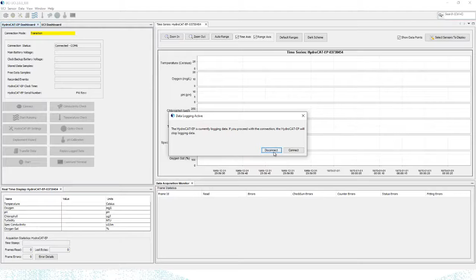And it's going to tell us a couple of things. So same thing, baud rate, COM port. Once UCI tries to connect to this HydroCAT EP, it's going to say, hey, this HydroCAT EP is currently logging data or is waiting to log data. If you proceed with this, it's going to pull it out of that logging state or that standby state, and you'll have to redo the deployment wizard. So if you don't want to do that, you click on disconnect. UCI will just fail to connect or choose not to connect. If you click on connect right here, UCI is going to connect to your instruments and pull it out of the logging state. Now we're sort of back at square one. You'll need to repeat the deployment wizard before you disconnect from UCI. Otherwise, the HydroCAT EP will not log when you expect it to.